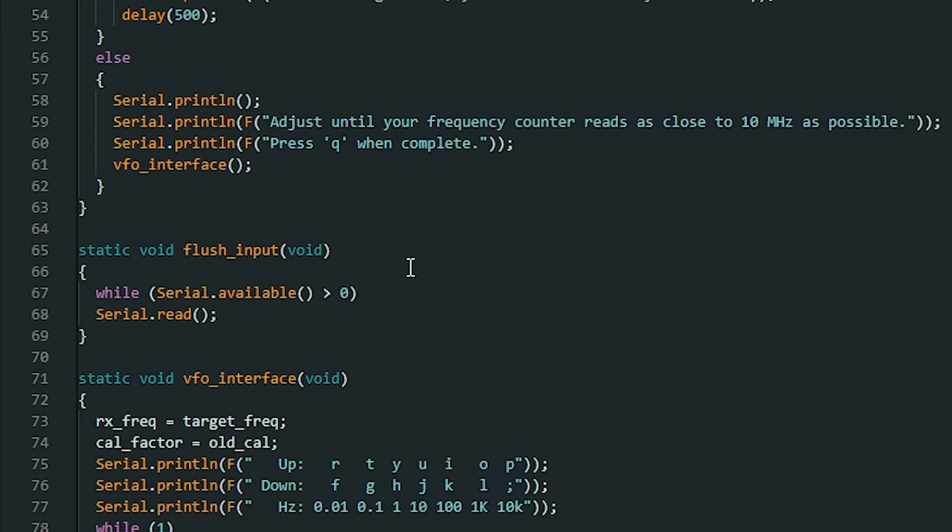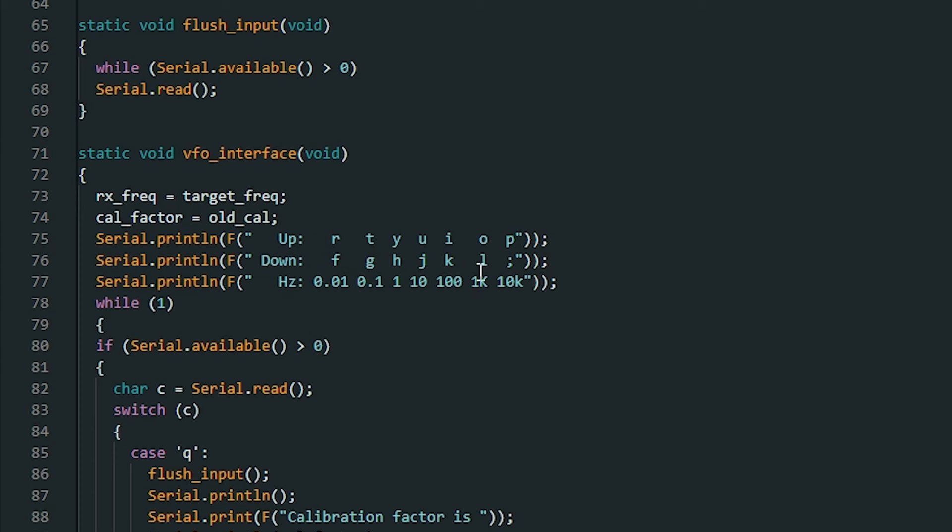Now ultimately what this does it generates a frequency on clock zero and what it is we're looking for 10 megs. So we're going to see our errors, they're going to be there. But what we do by pressing some of these keys and I'll show you exactly how to do that in a second, we can actually alter the frequency and then in return once we've got it on frequency we can get a calibration figure and we can use that in a code.